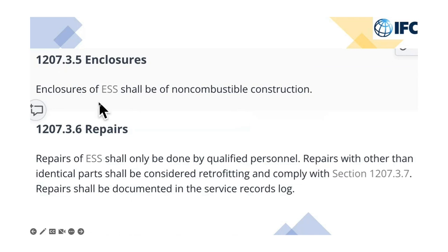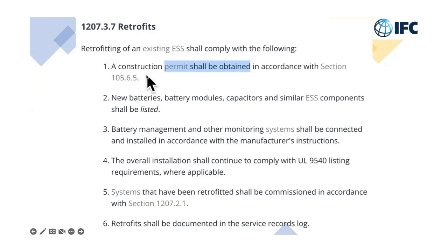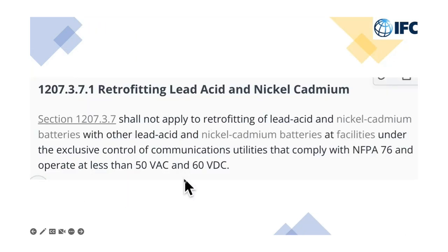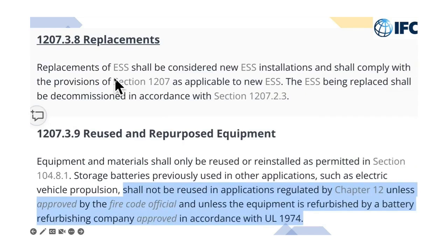And enclosures shall be non-combustible, repairs only by qualified personnel. And if you're going to do a retrofit, you need a permit, it says right here, and that does not apply to lead acid. Replacements should be considered a new installation. Repurposed and reused equipment, electric vehicle batteries, shall not be reused in applications regulated by Chapter 12 unless approved by the fire code official, unless the equipment is refurbished by a battery refurbishing company approved in accordance with UL 1974.